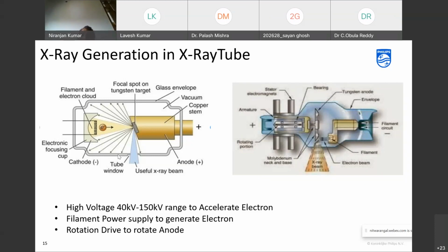X-ray imaging is exactly the same. So the heating area has to be as small as possible, so that the X-ray looks like it's coming from a point source, and the moment it is a point source, your image quality will be much better.